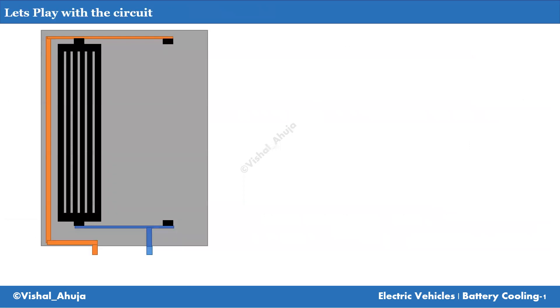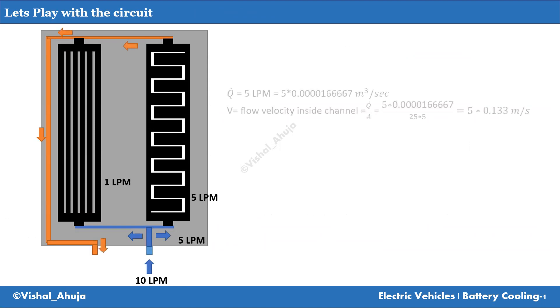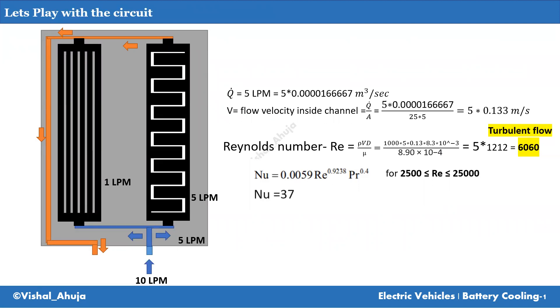We know the major resistance is coming from the flow side. Let's play with the circuit a bit. Instead of five channels, let's make a single channel, so all five LPM flows through a single channel. The velocity in that section will increase. We calculate the Reynolds number again, and now it is five times higher — 6060. This is no longer laminar flow, so the Nusselt number will not be a constant value; it will depend on velocity. Using the turbulent flow equation and considering water as a coolant, we get a Nusselt number of 37.